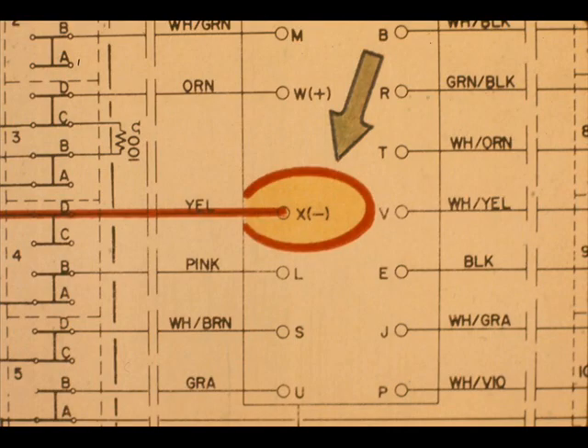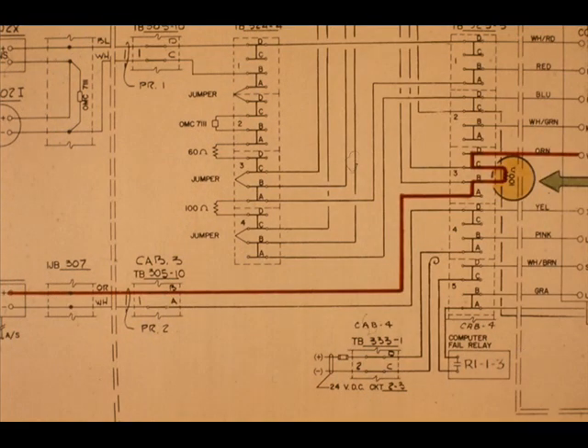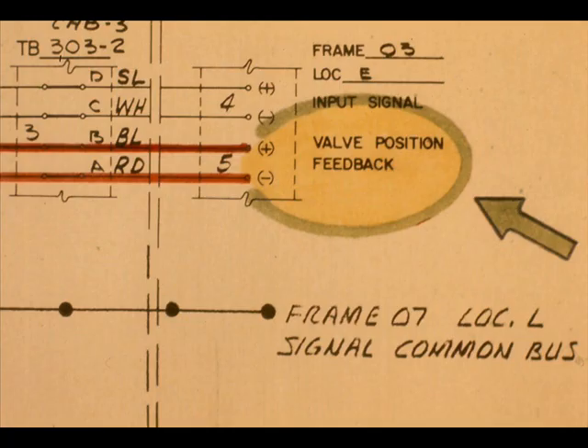The 10 to 50 milliamp controller output current signal flows from pin X of the controller through the I-to-P transducer, through a 100 ohm resistor to pin W of the controller. A 1 to 5 volt signal develops across the 100 ohm resistor. The computer senses this signal. This signal is called valve position feedback.